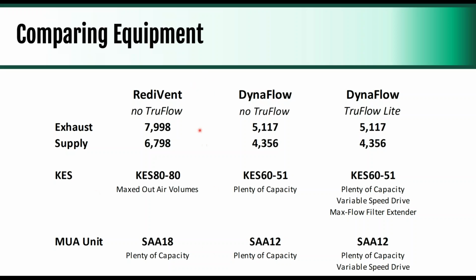So now as we go through, we compare equipment with the RediVent project. So that's the non-high efficiency. Your exhaust is 8,000 CFM. Your supply is just under 7,000 CFM. You've got what we call our KES 80, but it's maxed out. You've got no additional air volume or capacity in case the static pressure was calculated incorrectly. The makeup air unit, you're in what we call an SAA18 unit, so there's no real difference there.